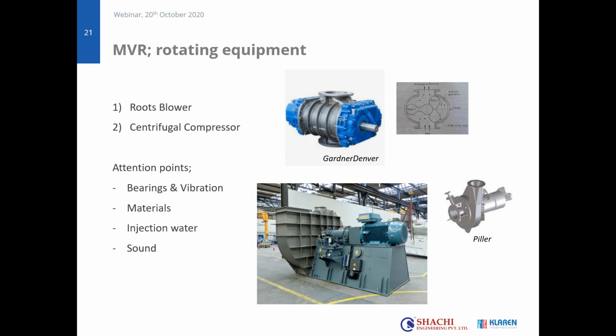And in the bottom picture, you see that this directly also shows a more sophisticated piece of equipment. And in fact, it is. It will no longer have roller bearings, but it will have sliding bearings. And that also means that you need lube oil and a proper lubrication system to make sure that the shaft is supported well. And even in case of a power failure, you need backup systems to make sure that the shaft remains rotating and lifted in its bearings. Otherwise, it could sink through these white metal bearings and lead to a lot of damage.